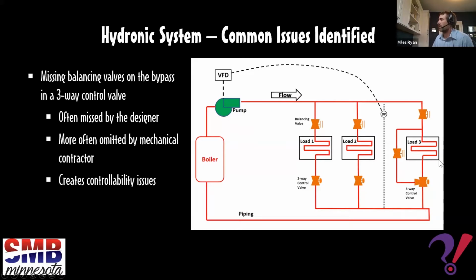And then you probably want to put a little safety factor on there as well. So oftentimes on a variable speed system like this, this one is cranked down even more to have an even greater pressure drop across it than its respective coil, because really it's just there as a path of flow in case everything else shuts off in the system. So it's a little bit different technique depending on variable speed versus constant speed hydronic systems.